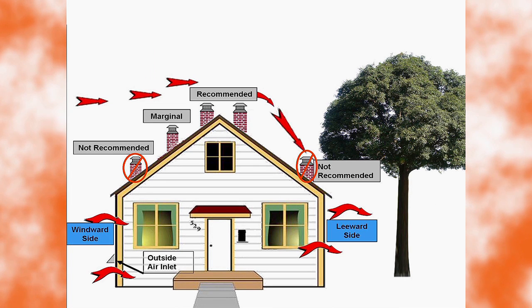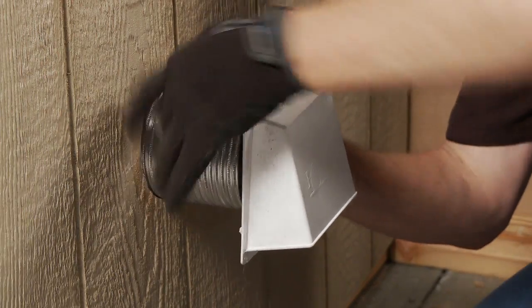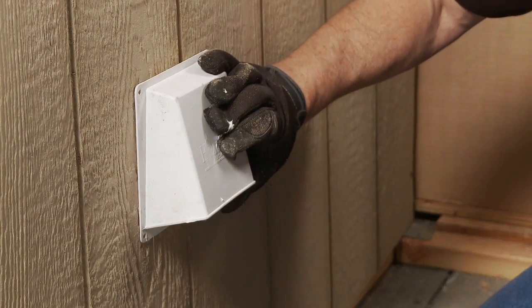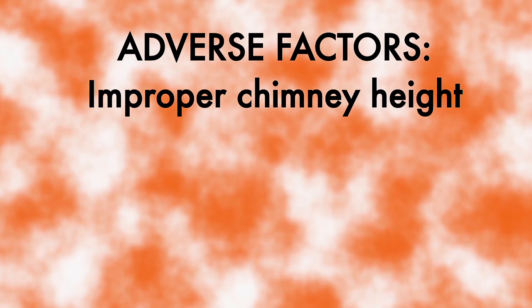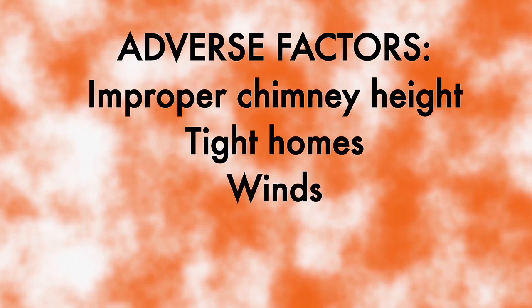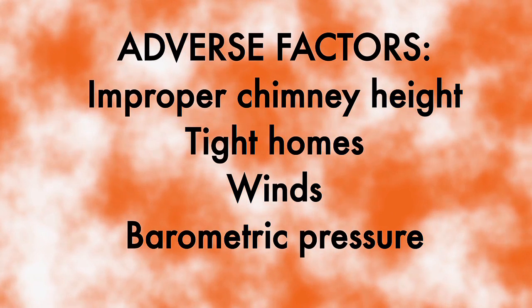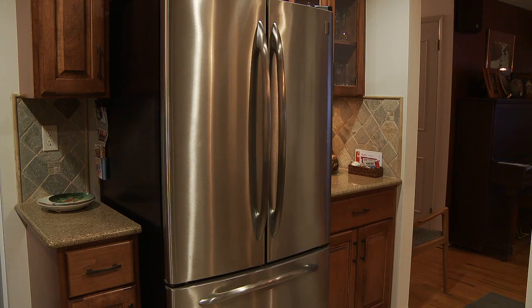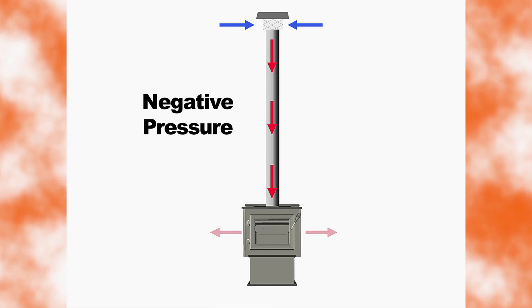Draft continually moves fresh combustion air into the stove and hot exhaust gases out of the stove. Without this constant air flow, the fire will go out or burn with less than desirable expectations, such as smoky stove pipes or dirty door glass. Installing the venting termination near the roof peak on the leeward side, and the outside air intake on the windward side of the house, will get the best results. See the manual for other termination recommendations. Draft can be adversely affected by improper chimney height, a tightly constructed home that prevents enough fresh air from entering the stove, winds that pressurize the chimney, and barometric pressure changes.